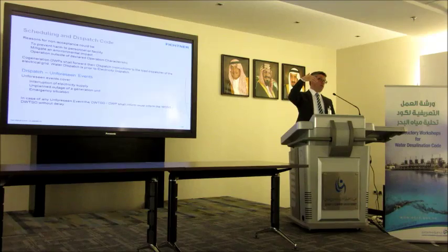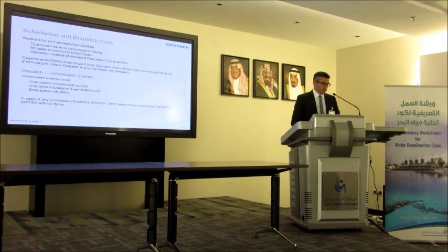This gives the load dispatcher for electricity the basis to dispatch a cogeneration plant on optimized cost, in order to avoid that steam gets dumped in the dump condenser or is not utilized in the steam turbine, and to dispatch cogeneration plants in the most optimum operation mode on the basis of the water dispatch.